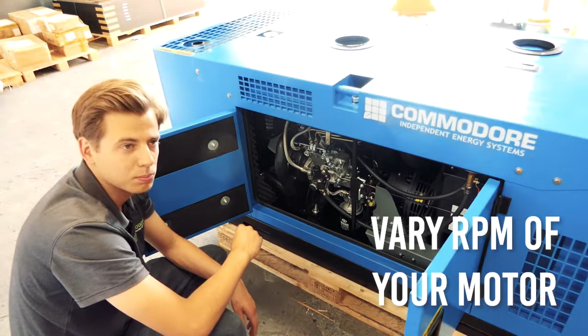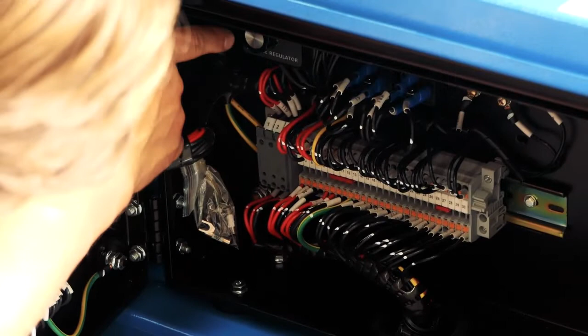So sometimes the voltage level in the generator might get a little bit out of sync as well, if it gets knocked around in transit or similar. So the good thing about these is they've just got a voltage adjustment dial behind the screen, so it's really easy to tune it if it ever needs to. So just pop this little panel here. It opens up, and it's just up in this top left hand corner that's labelled voltage regulator, and you can just adjust that dial to move it up and down.